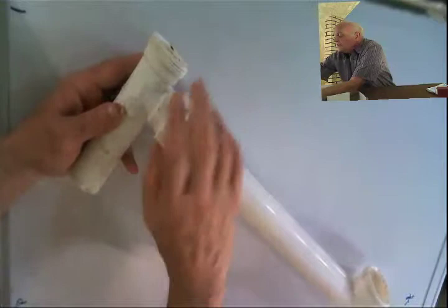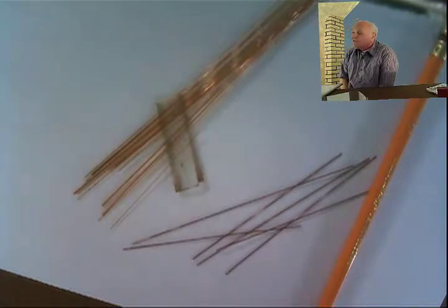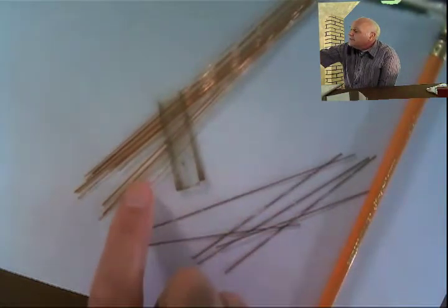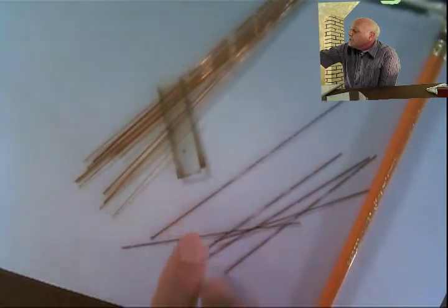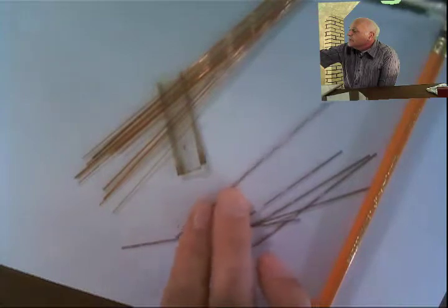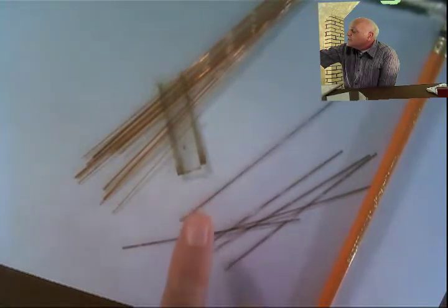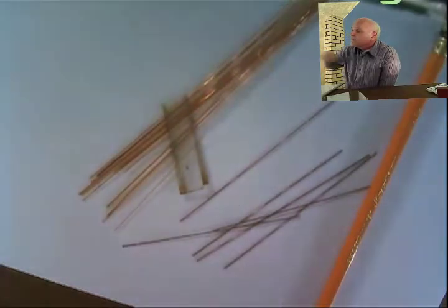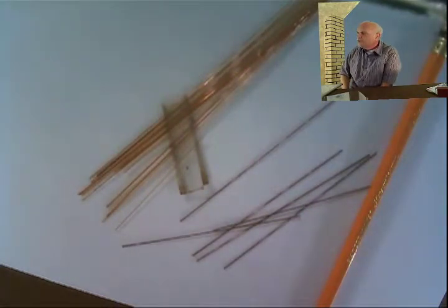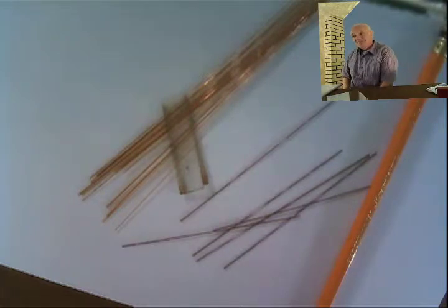The technology, the engineering for the GC column, is identical. Let's take a look at the column itself. The column is so small it's hard to believe that it's actually hollow. This is the standard 8270 column. This I believe is a megabore—I found these in a file so I'm not exactly sure, but I think this is the megabore from the 8240, which is the volatile GC-MS. But it's small. It's small to the point that it's just incredibly small, and it's 30 meters long.